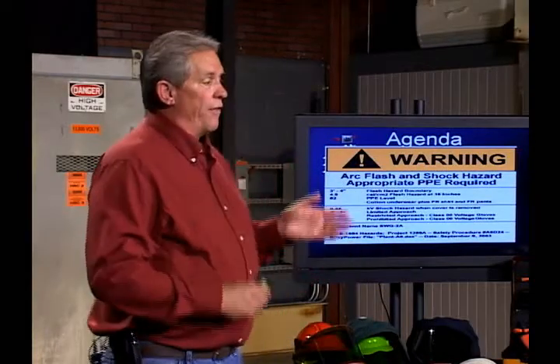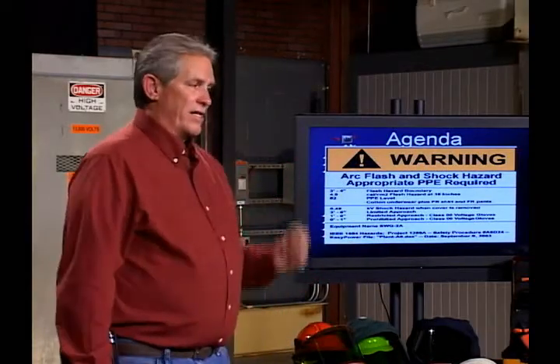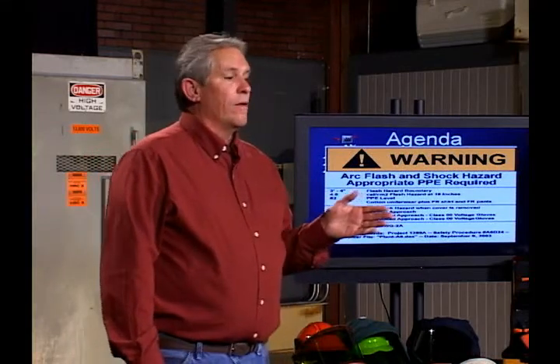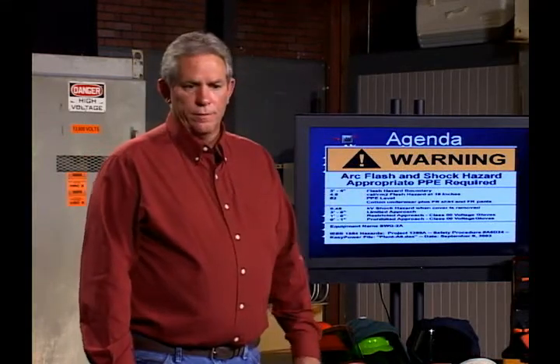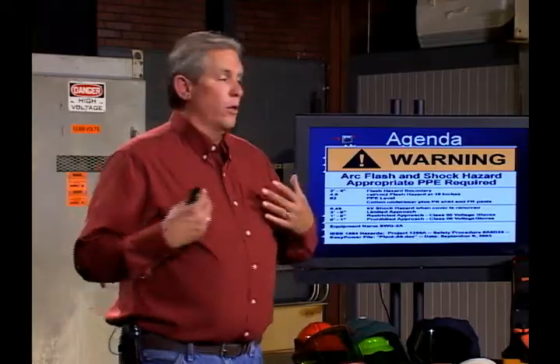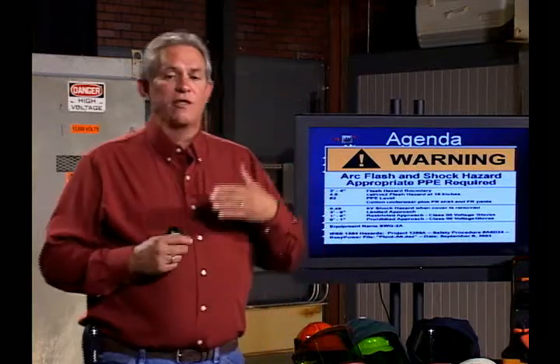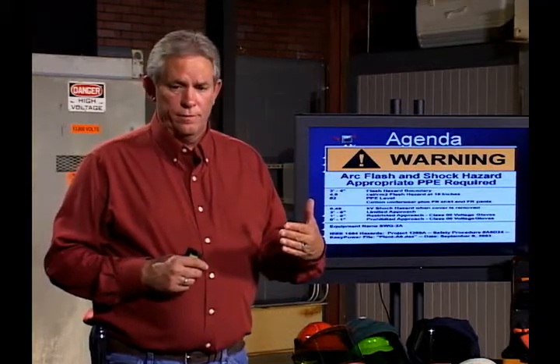Any closer than that 3 feet 4 inches, that same unprotected skin will now get a 3rd-degree burn. So I must have on the proper PPE — the FR-rated shirts, pants, or suit, whatever it might be — in order to cross that flash protection boundary.